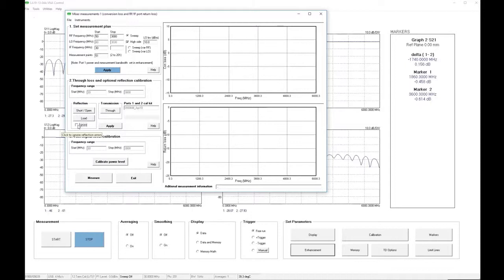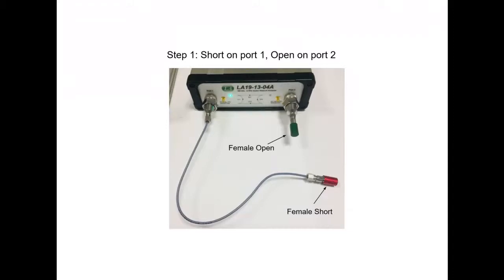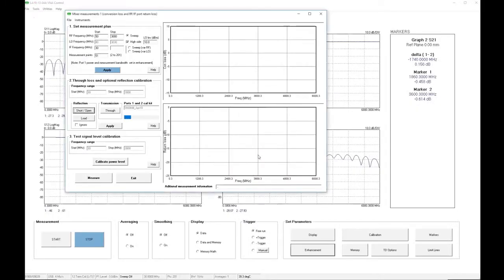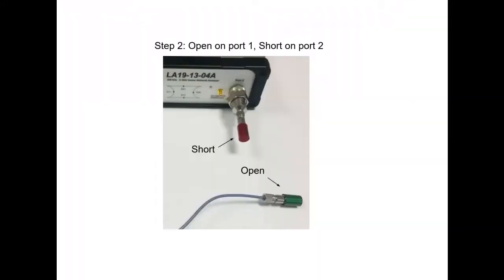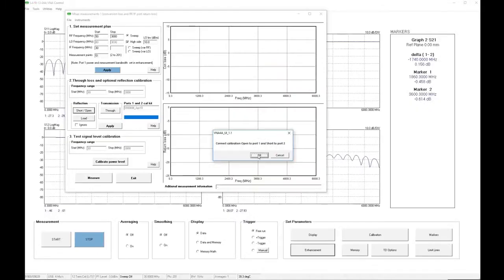So we can start by clicking this box at the top here that says Short Open. And this tells us that we need to connect a short to port 1 and an open to port 2. And we can see here in this photograph an example of what that would look like. Okay, so after having connected the standards, we click OK, and the measurement is done. The next thing is to reverse the calibration standards, so the open now goes on port 1 and the short on port 2. Here we are. This is what we need to connect to the ports. Once the standards are connected, we click OK, and the measurement is done.